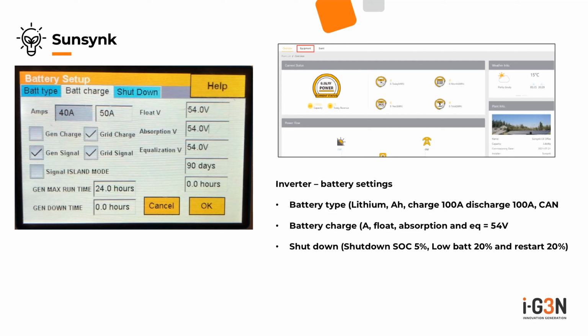In the battery charge tab, put in your amps for charging, float and absorption - everything defaults to 54. Then on the shutdown screen, set shutdown to 5%, low battery at 20%, and restart at 20% as well.